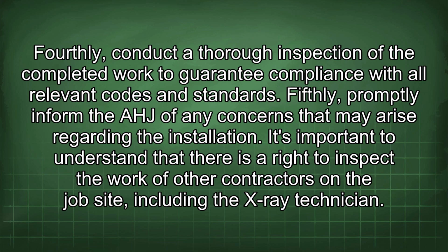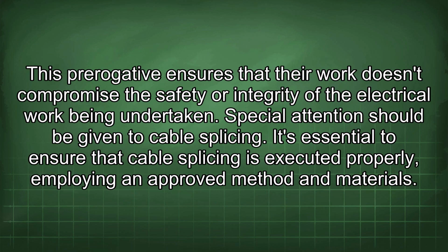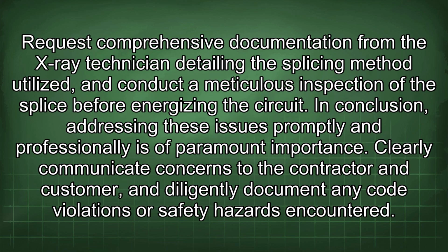It's important to understand that there is a right to inspect the work of other contractors on the job site, including the X-ray technician. This prerogative ensures that their work doesn't compromise the safety or integrity of the electrical work being undertaken. Special attention should be given to cable splicing. It is essential to ensure that cable splicing is executed properly, employing an approved method and materials. Request comprehensive documentation from the X-ray technician detailing the splicing method utilized, and conduct a meticulous inspection of the splice before energizing the circuit. In conclusion, addressing these issues promptly and professionally is of paramount importance.